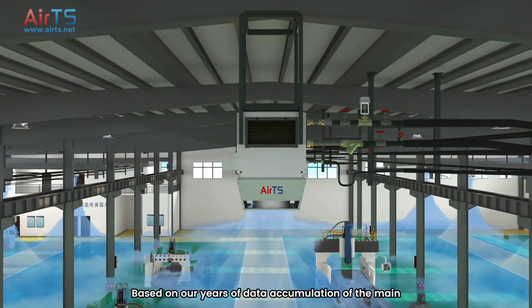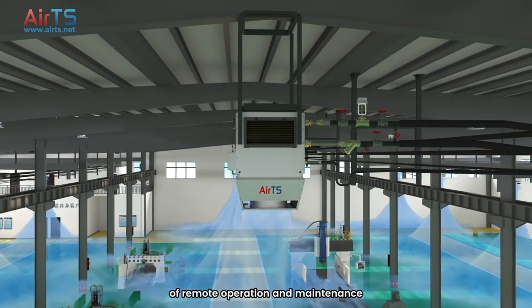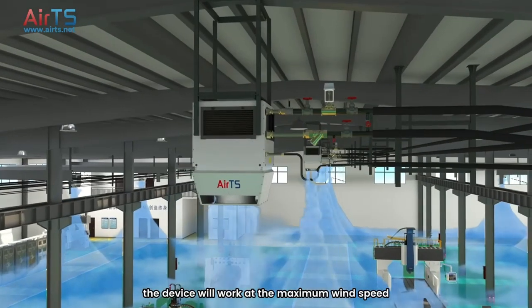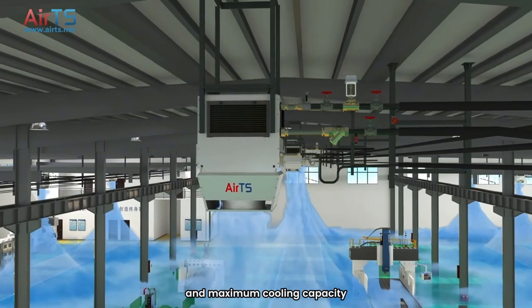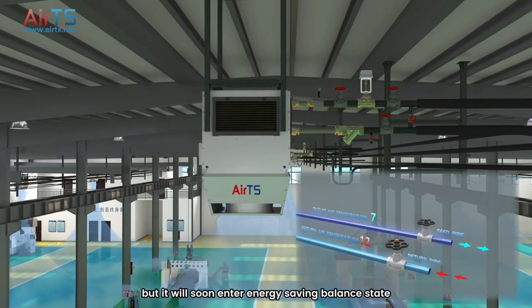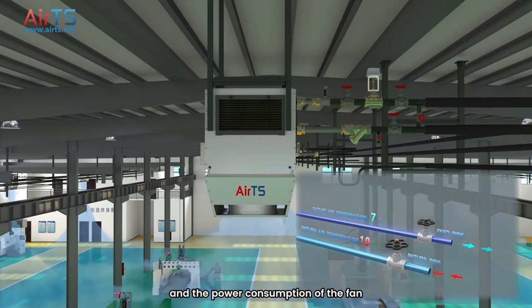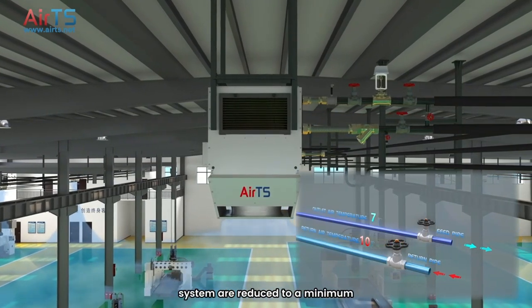Based on our years of data accumulation of the main control system and the experience of remote operation and maintenance, the device will work at the maximum wind speed and maximum cooling capacity when it is initially started, but it will soon enter an energy-saving balance state, and the power consumption of the fan and the cooling capacity from the water system are reduced to a minimum.